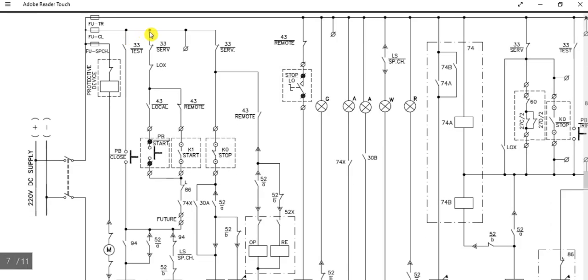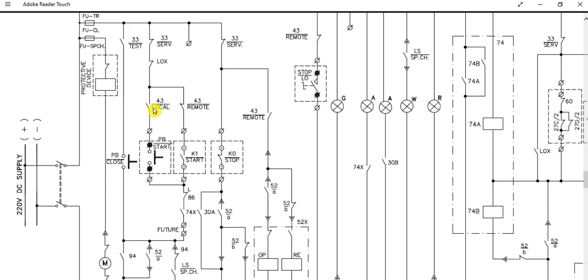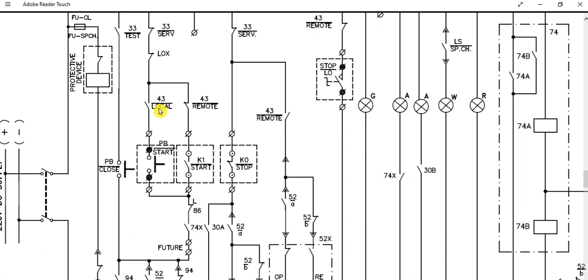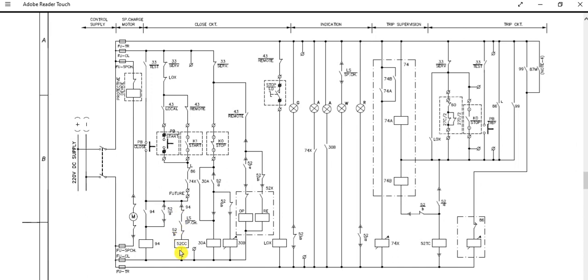If the breaker is in service position, the path comes this way. Now, if the control selector switch is in local position — meaning you want to operate from the local switch — this path will be followed. When you press the start push button, the path goes through and it will energize the closing coil of the breaker.